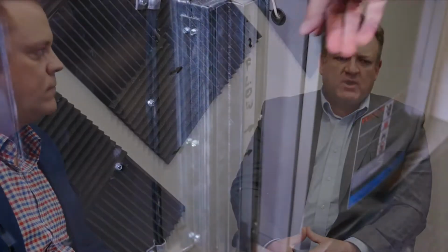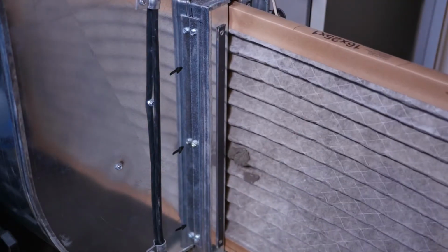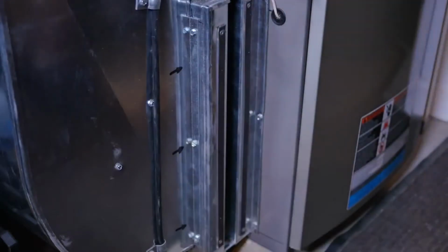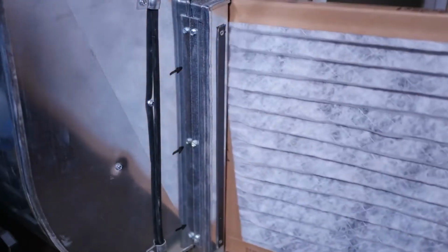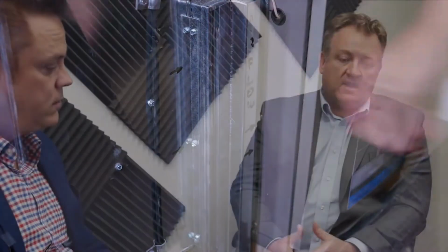If you've seen the CDC and ASHRAE, they have recommended that people increase their MERV ratings on filters, which means put a more effective filter in place on your HVAC system. That's causing some problems in the industry because by putting a higher rated filter in a system, you're creating a pressure or a back pressure. You're creating different CFMs that the motors can now blow through, creating pressure issues inside of buildings.